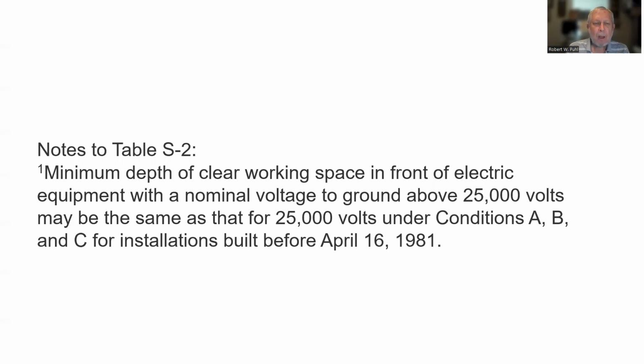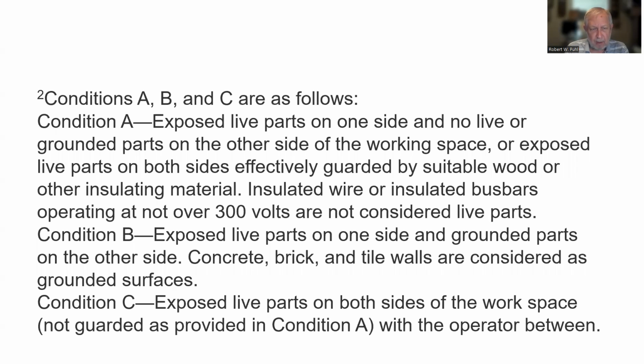This is the notes of that table. Minimum depth of clear working space in front of electric equipment with a nominal voltage to ground above 25,000 volts may be the same as that for 25,000 volts under conditions A, B, and C for installations built before April 16, 1981. Conditions A, B, and C are as follows. A, exposed live parts on one side and no live or grounded parts on the other side of the working space, or exposed live parts on both sides effectively guarded by suitable wood or other insulating material. Insulated wire or insulated bus bars operating at not over 300 volts are not considered live parts.